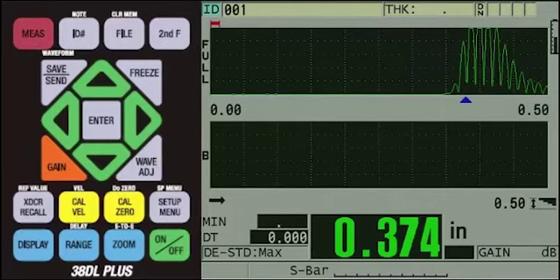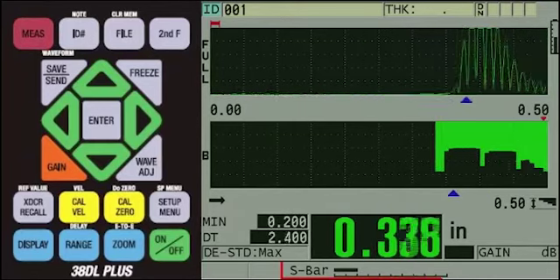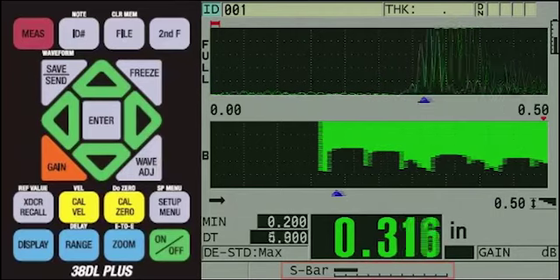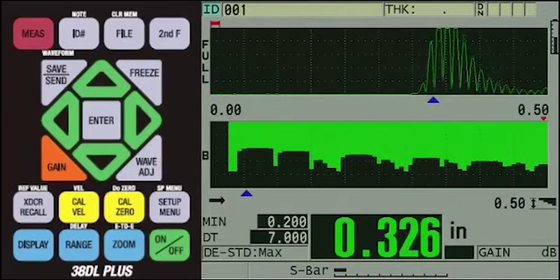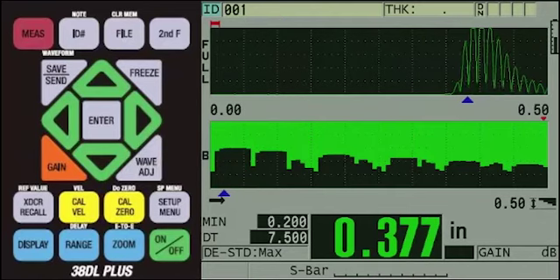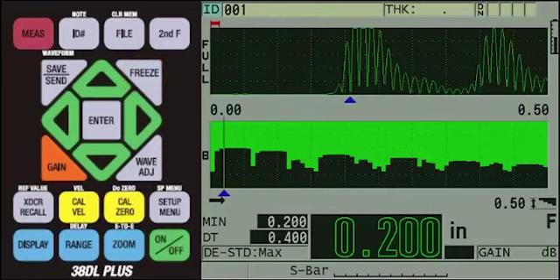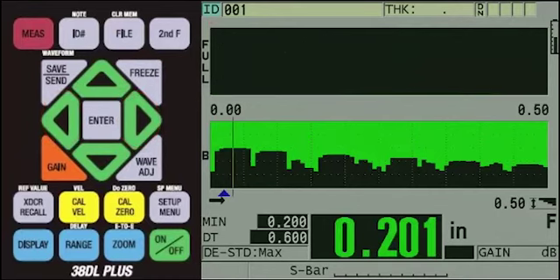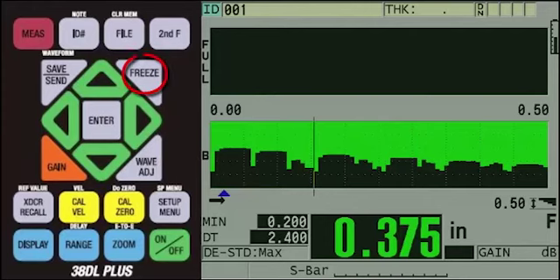You can watch the speed bar at the bottom of the screen to make sure you do not move the buggy too fast. Since we have Freeze Review turned on, we can press the Freeze key at any point in the scan and then use the left and right arrows to review different areas of the scan. The gauge displays the thickness in that spot and the distance the buggy has traveled to reach that spot. We can then press the Freeze key again and continue scanning the plate.